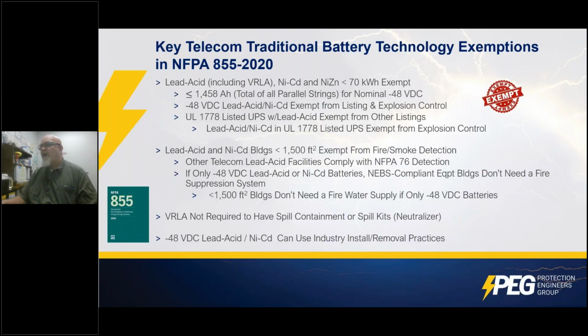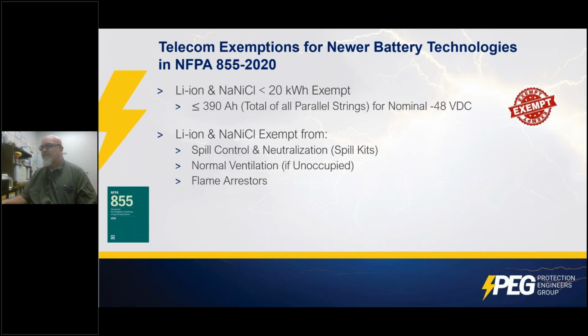And you don't have to have a fire water supply for really, really tiny telecom buildings. VRLA was not required to have spill containment, which makes sense since it's an immobilized electrolyte and can only spill a few drops. And negative 48 volt DC systems can use industry install and removal practices. Next slide. In other words, rather than having to use the install and removal practices in NFPA 855 and come up with brand new stuff, they could use existing.